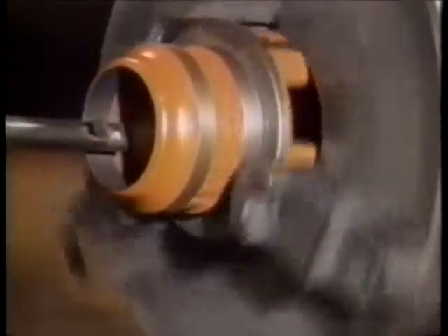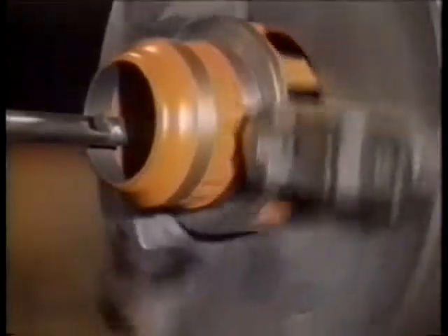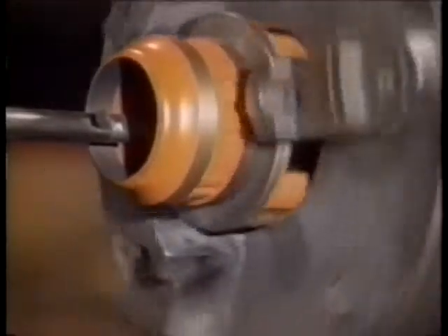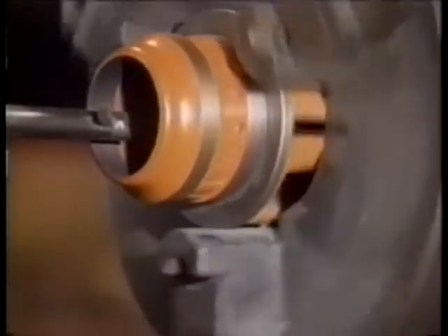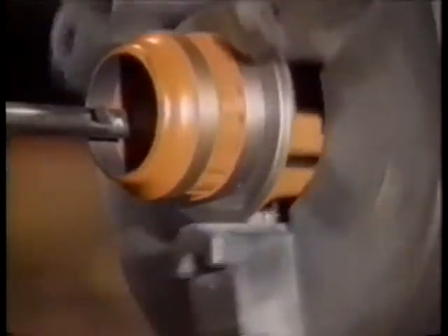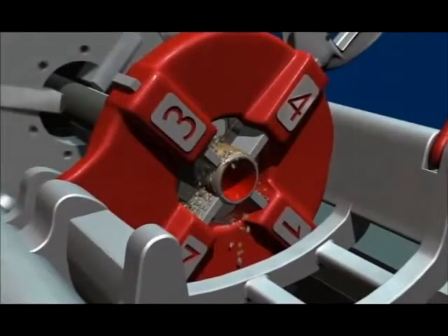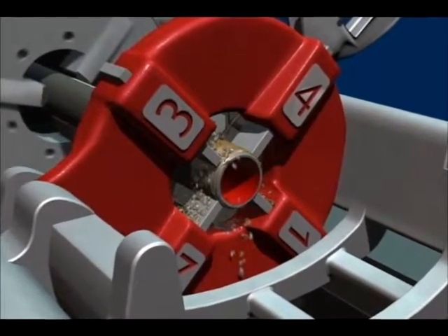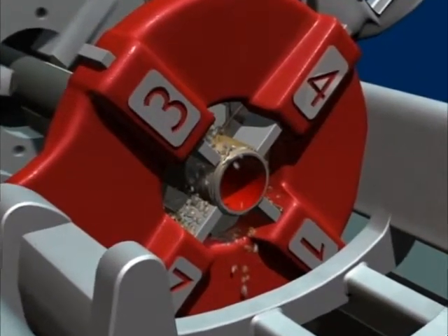If a threader with a tight fitting die head is to be used like many hand held models, it is necessary to machine out the interior diameter of the stationary guide approximately twelve one hundredths of an inch to allow for clearance of the PVC coating. Prior to machining the pipe guide, take note of the sequence in which the dies are removed. After machining, replace the dies in the proper sequence.